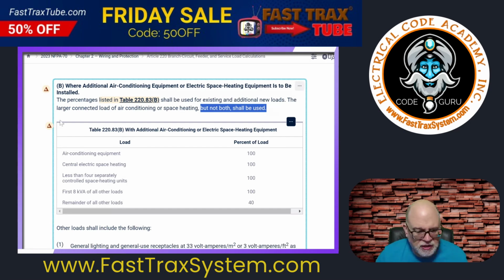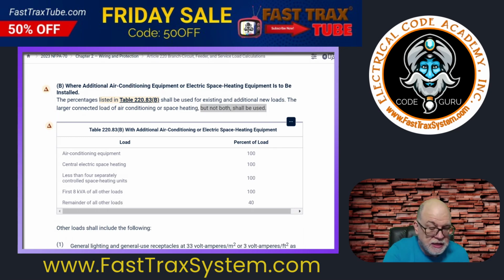Okay, so let's look now. I'll give you a look at what it's going to look like in the 2026 edition. Hopefully this is not confusing. The easiest way I can tell you is to just do the optional method like in part A, as you normally would in this example, and then take the heating or the air conditioner, whichever is larger, and add that at 100% to the totals that you got when you did the first 8,000 at 100% and the remainder at 40%. After you get a value, you add your AC or heat to it at 100%.